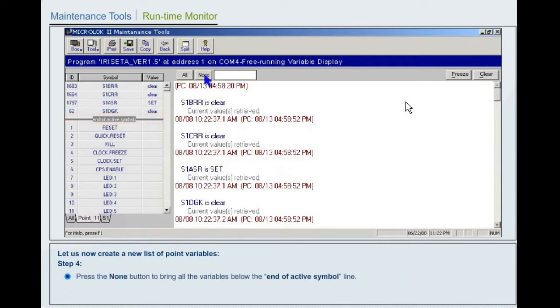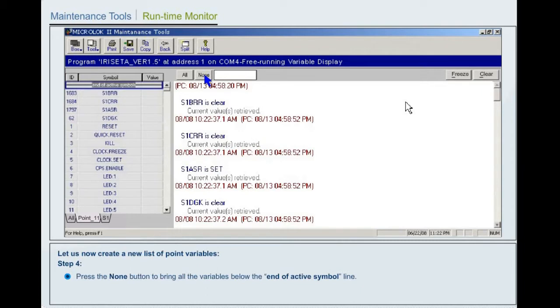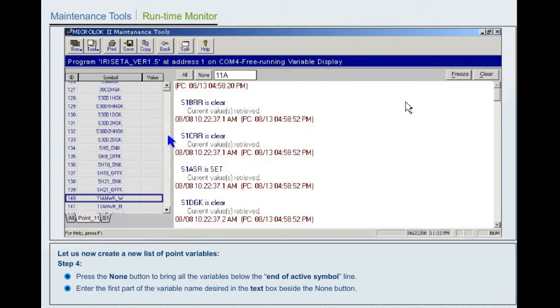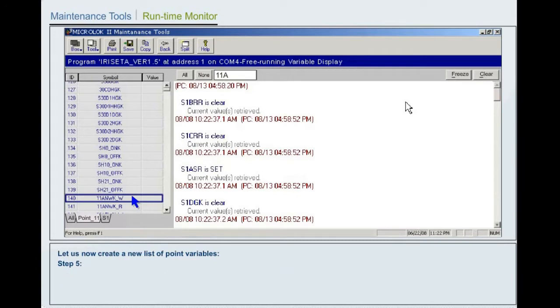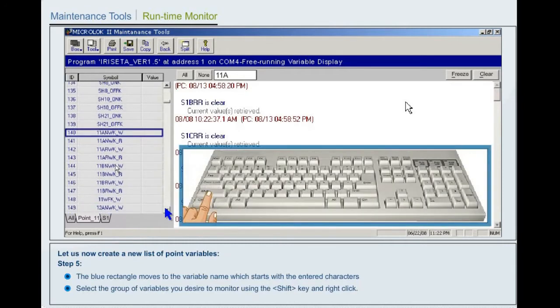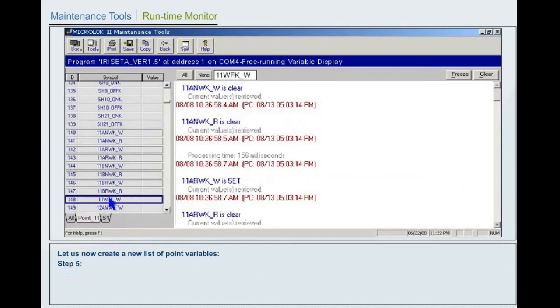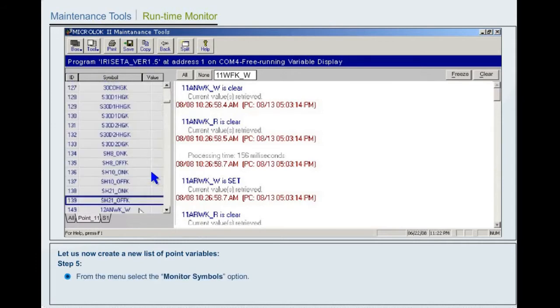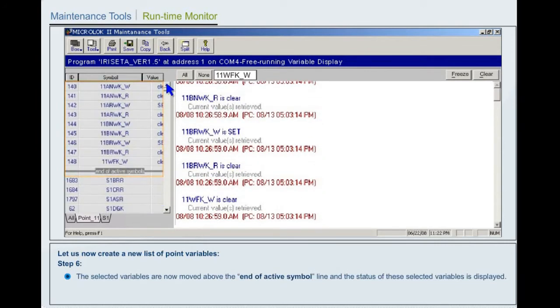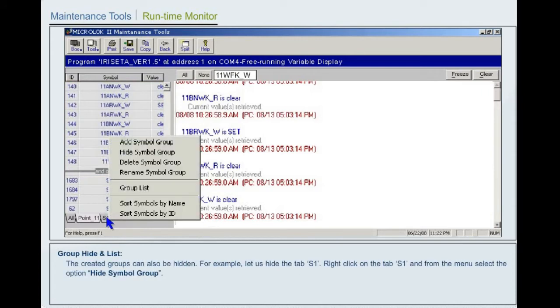Step 4. Press the None button to bring all the variables below the end of active symbol line. Enter the first part of the variable name desired in the text box beside the None button. Step 5. The blue rectangle moves to the variable name which starts with the entered characters. Select the group of variables you desire to monitor using the Shift key and right-click. From the menu, select the Monitor Symbols option. Step 6. The selected variables are now moved above the end of active symbol line and the status of these selected variables is displayed.